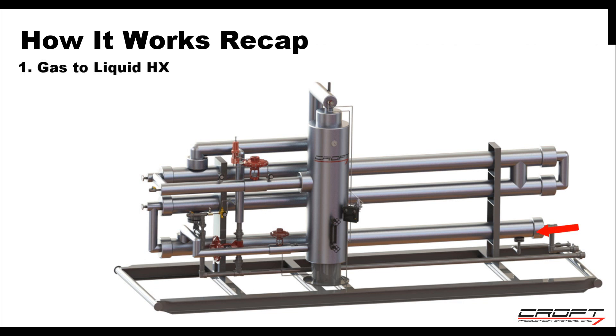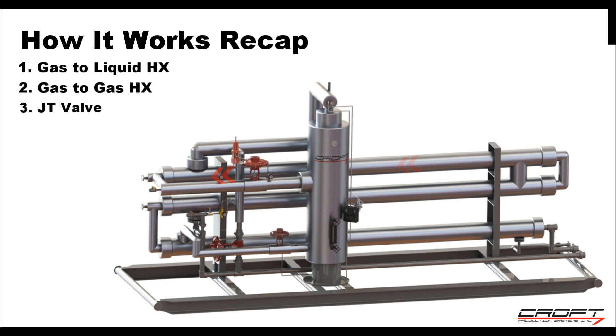Rich, hot gas enters the liquid-to-gas heat exchanger where it is cooled by cold NGLs coming from the cold separator. The rich gas will then continue to the gas-to-gas heat exchanger where it is cooled by lean cold gas coming from the cold separator. The gas will then go through a JT valve where it takes a pressure drop. We will use the chilling effect of that pressure drop to chill down the gas and ultimately reach our cold separation temperature. The cold gas will then go into the separator where the liquids are separated out of the gas. The liquids will fall to the bottom of the separator and be dumped down into the liquid-to-gas heat exchanger where the cold fluids are used to cool the incoming hot gas.